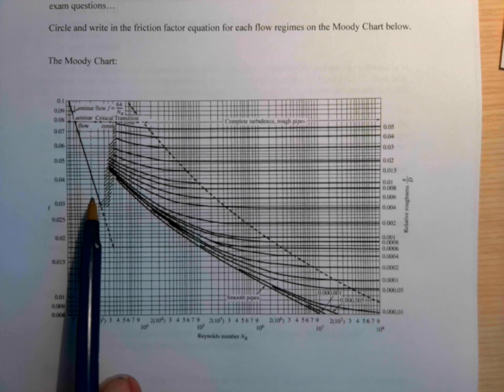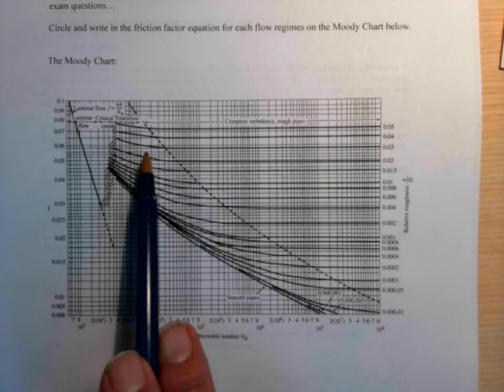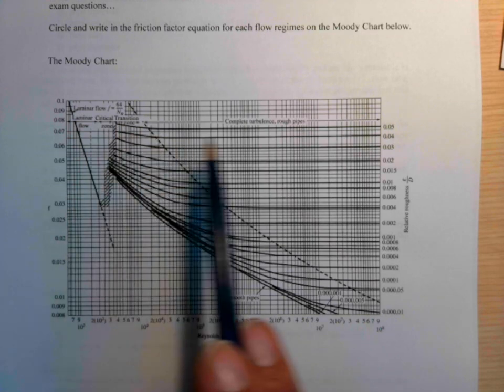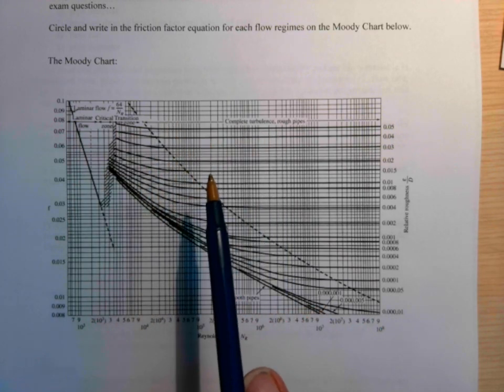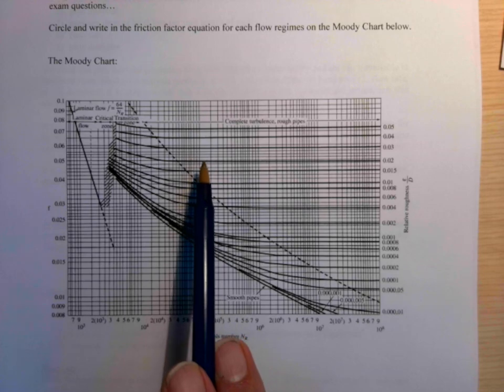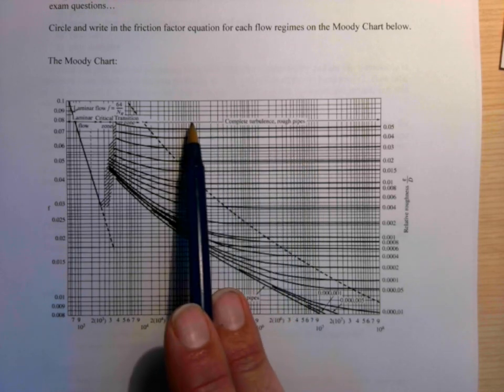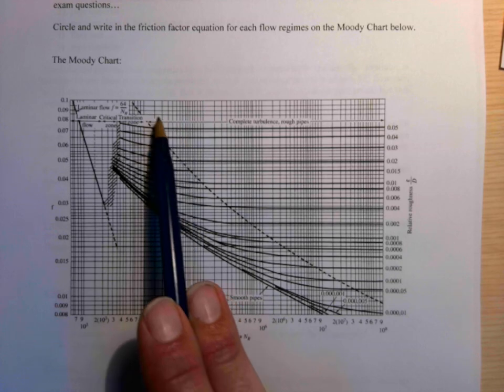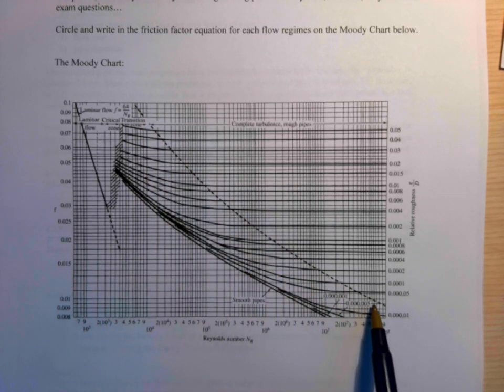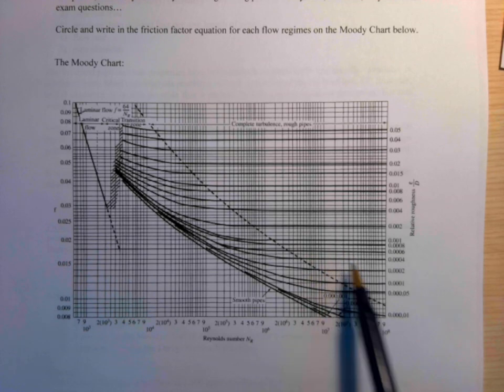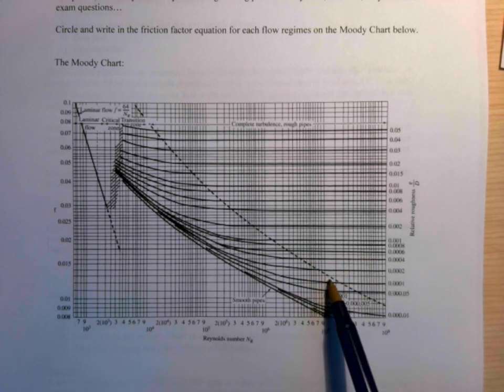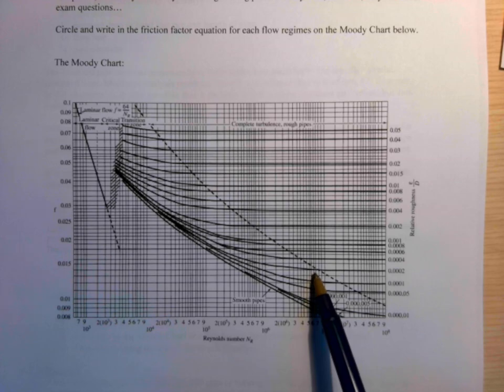Laminar flow is here on the left side, and then turbulent past this critical zone. For turbulent, there's three different possibilities. We have the rough pipe, complete turbulence, where these lines are all flat, and that's to the right of the dashed line. You can see how they all flatten out once you reach the dashed line, maybe a little bit to the left of it even.